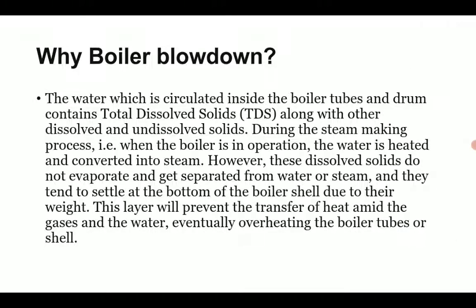So why boiler blowdown? The water which is circulated inside the boiler tubes and drum contains total dissolved solids along with other dissolved and undissolved solids. During the steam making process, that is when the boiler is in operation, the water is heated and converted into steam. However, these dissolved solids do not evaporate and get separated from the water or steam, and they tend to settle at the bottom of the boiler shell due to their weight. This layer will prevent the transfer of heat between the gases and water, eventually overheating the boiler tubes or shell.